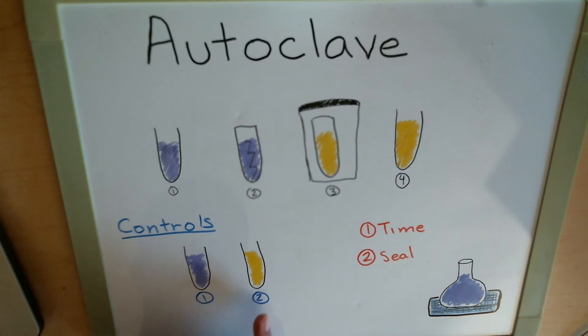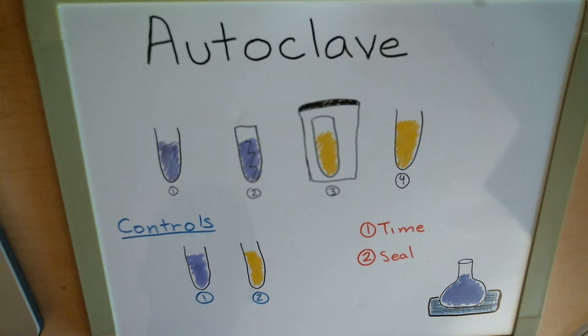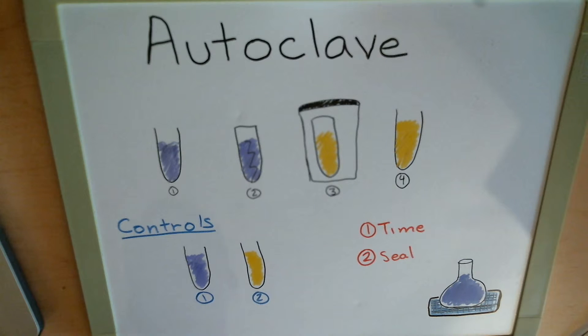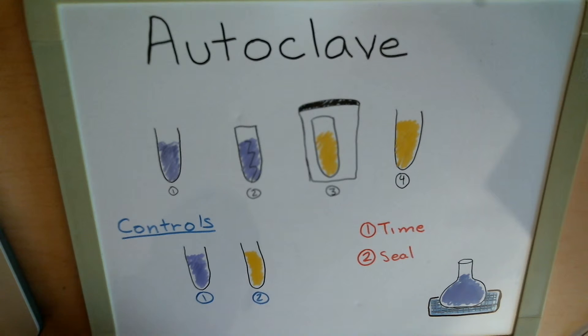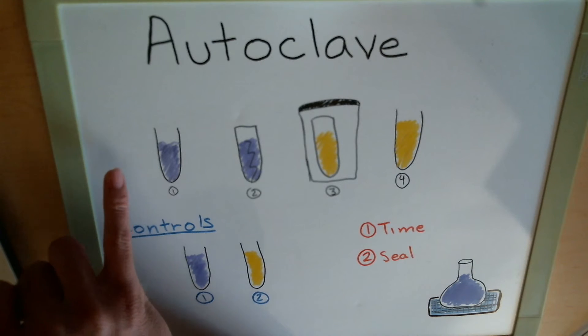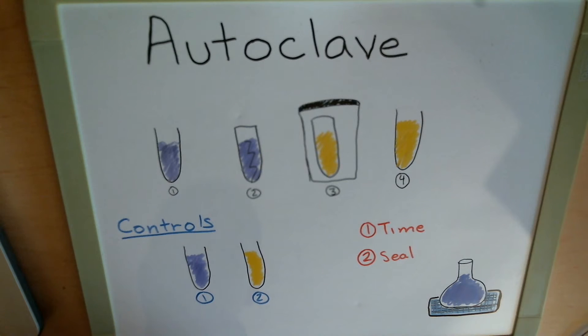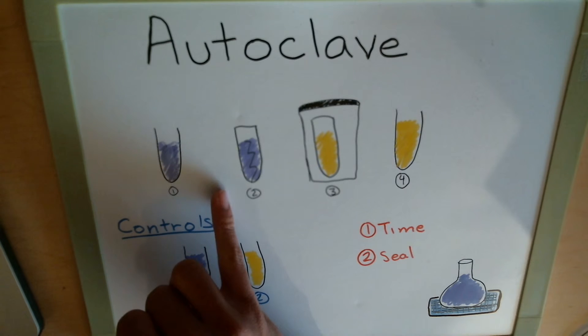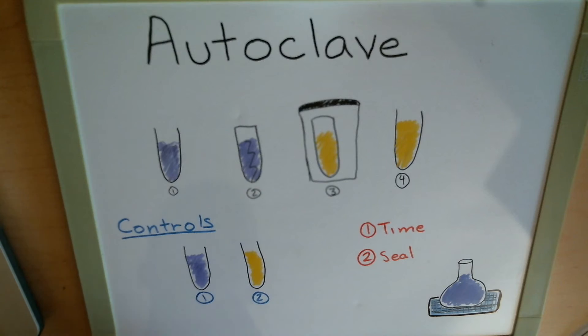Here's what the demo goes over. The positive control is the yellow one, indicating bacterial growth. The negative control is purple, indicating all bacteria have been killed. The first sample is all purple and unsealed — exactly as expected, since nothing prevents the steam from getting in and killing the bacteria. In the second sample, we attempted to close the test tube, but the pressure caused the test tube to crack, resulting in steam getting in and killing the bacteria.